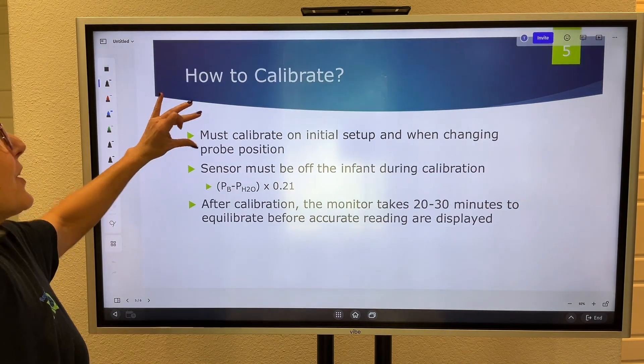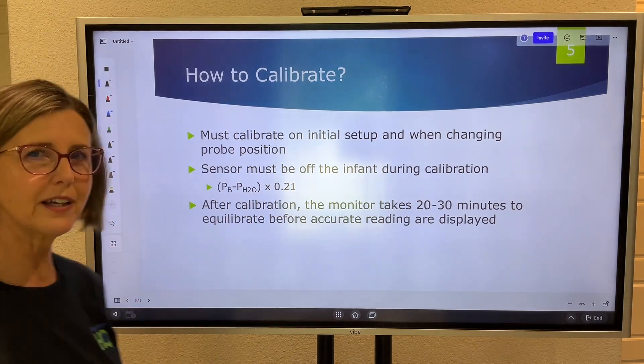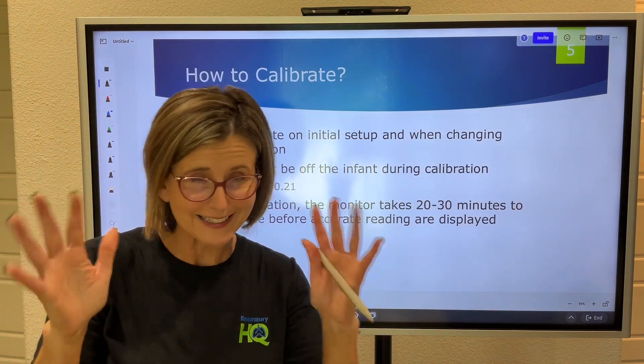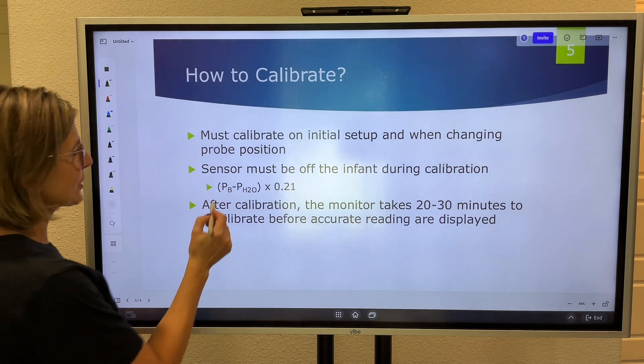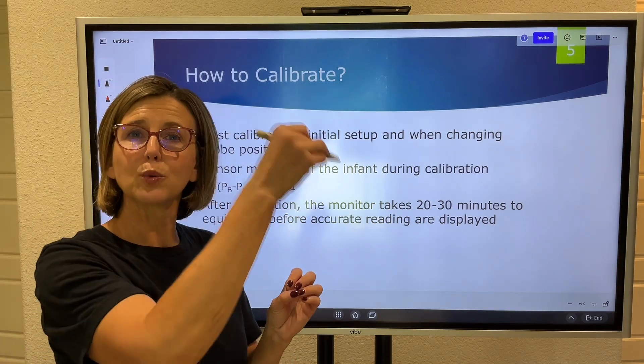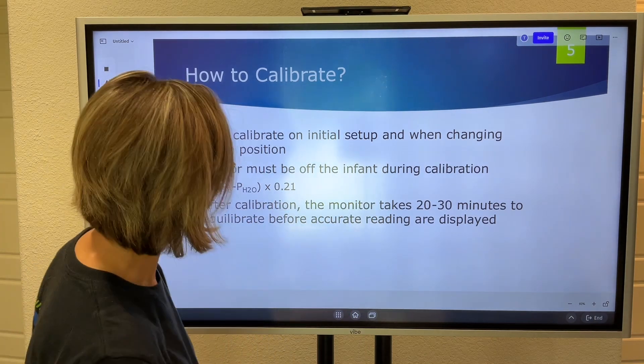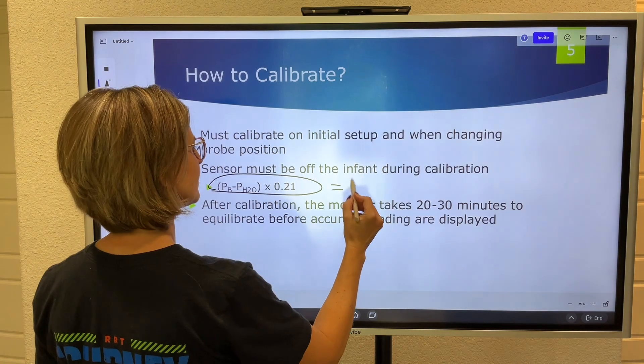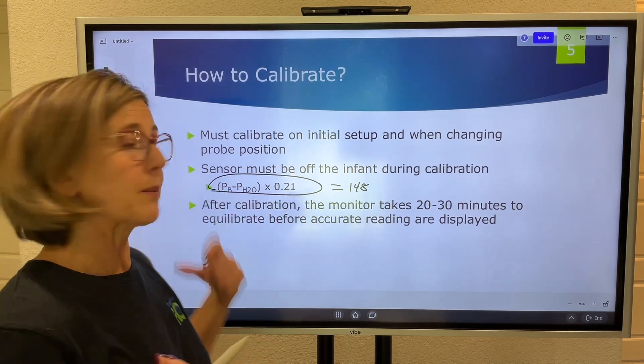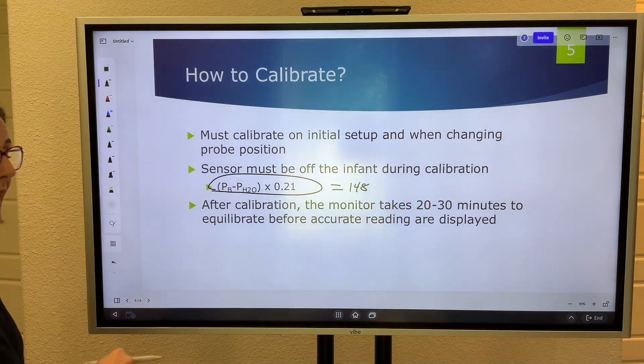How do you calibrate? Calibrate on initial setup and each time you change the probe position. Take it off the baby, hold it up to room air, and press the calibration button. The machine takes the current barometric pressure, subtracts water vapor pressure, and multiplies by 21% (0.21). For a PO2 electrode, assuming barometric pressure of 760 mmHg, this comes out to roughly 148–150 mmHg. Once it reads that value, it's calibrated and you can place it back on the baby.